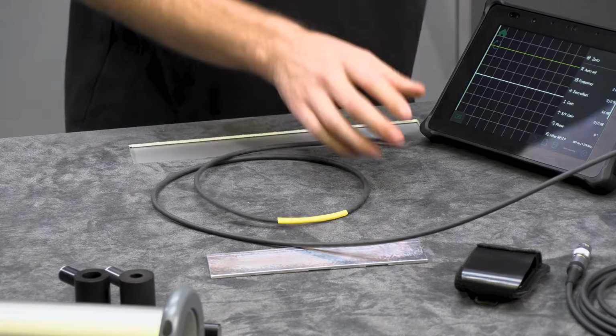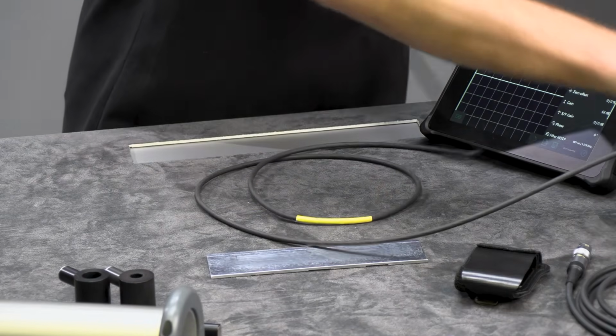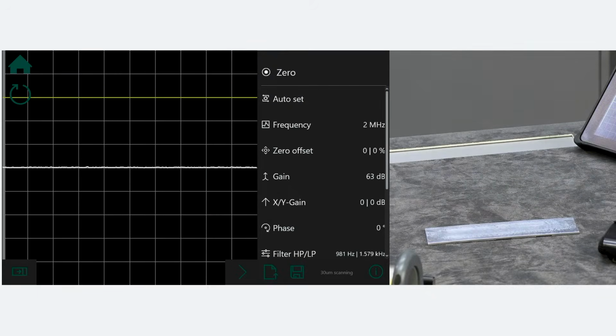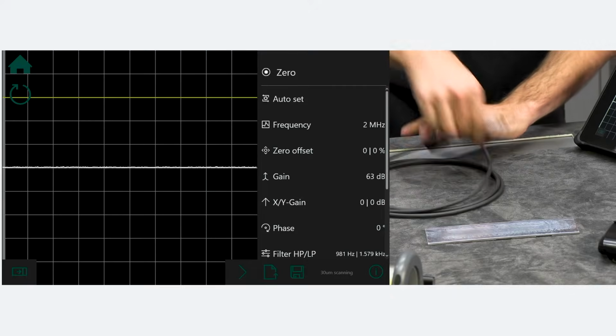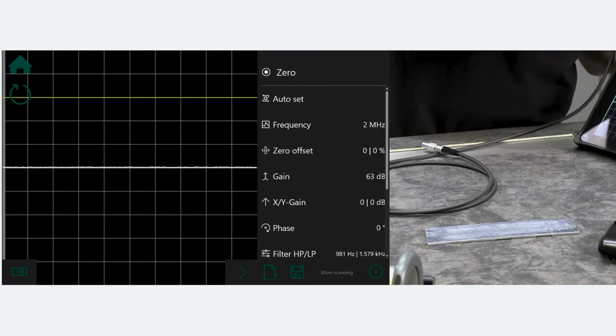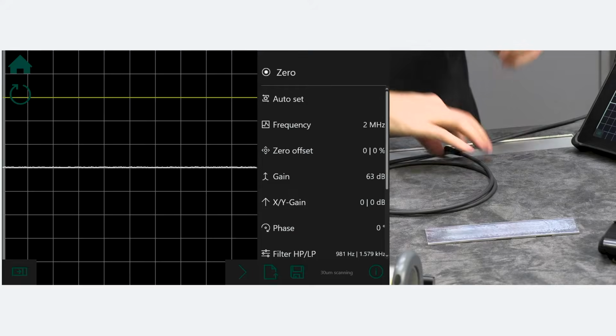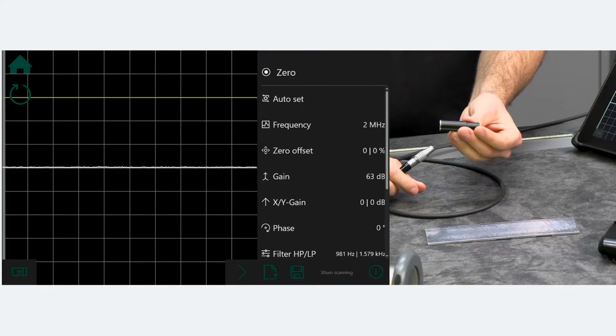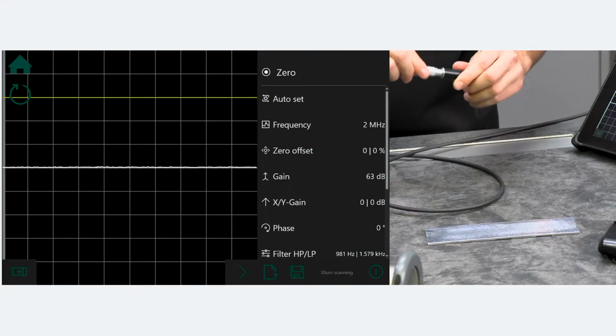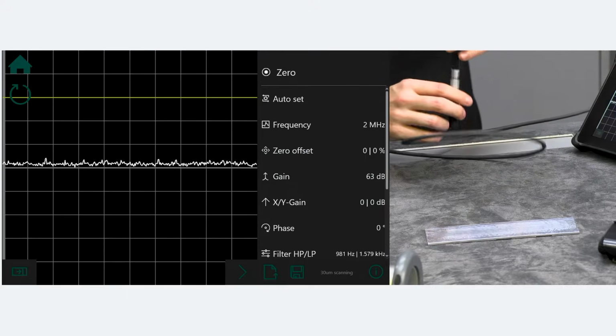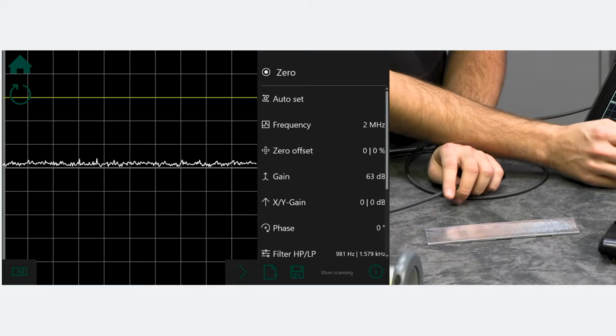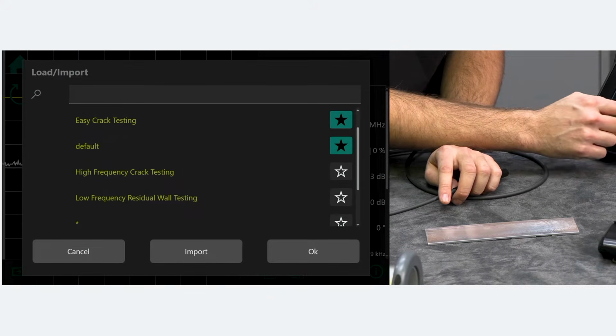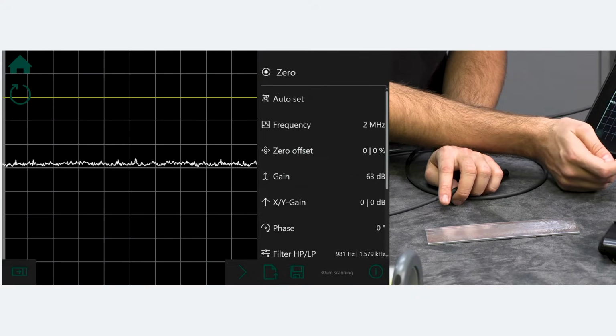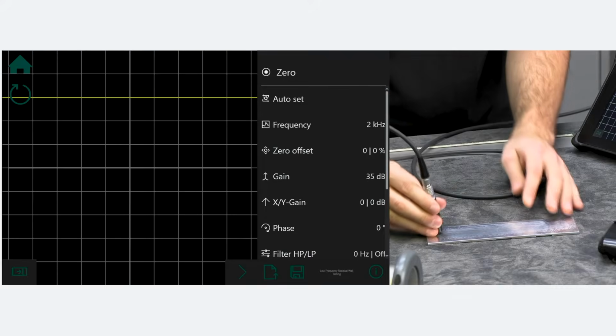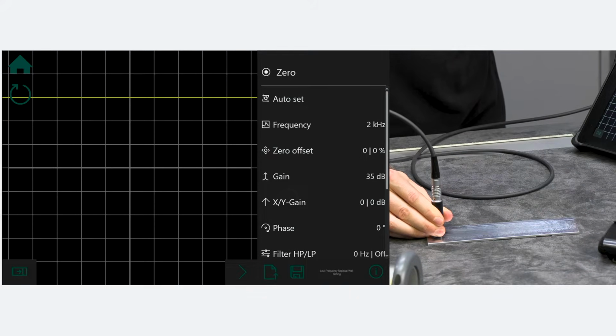I will switch to the correct probe. One moment. Okay, so for that we will use a low frequency testing probe. This probe is optimized to test at 2 kilohertz, but you can also use it on other test frequencies. We will load the program I prepared for that. So we have low frequency residual wall testing. And we put the probe on the material, make 0.